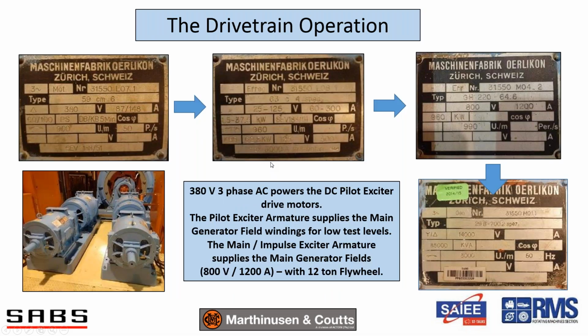Now, how does the drivetrain work? For the generator fields, you need 800 volts at 1200 amps. That's the full rating of the field. So how does that come about? Well, it's basically with the DC exciters I showed you. Here we go. It's a 960 kilowatt, 1000 RPM machine, and it develops 800 volts at 1200 amps. And of course, there are two of them, fitted to the same shaft.